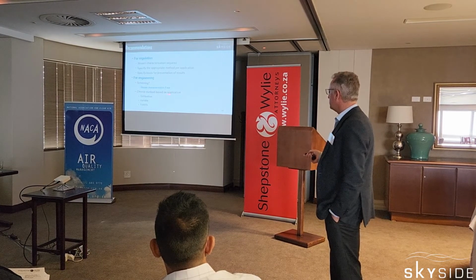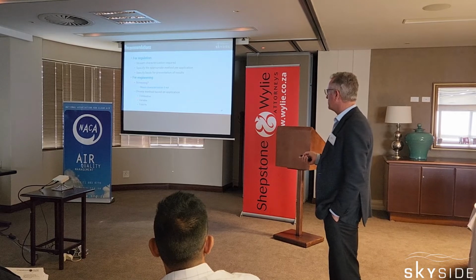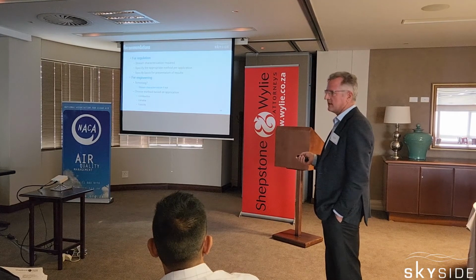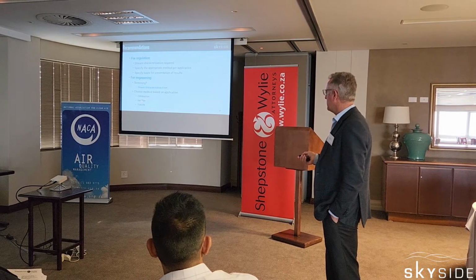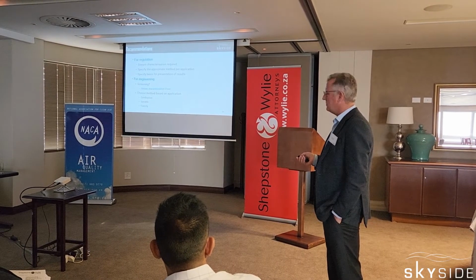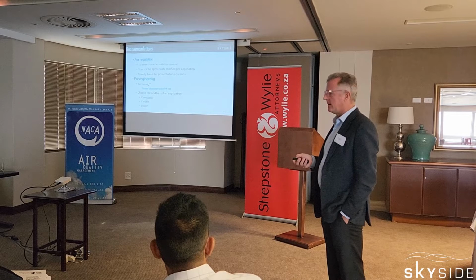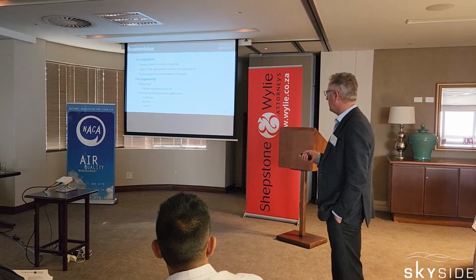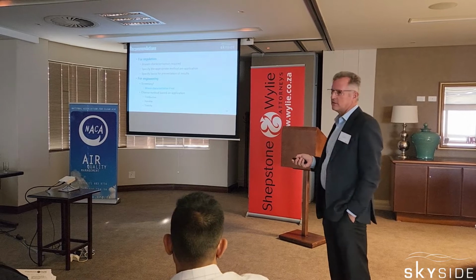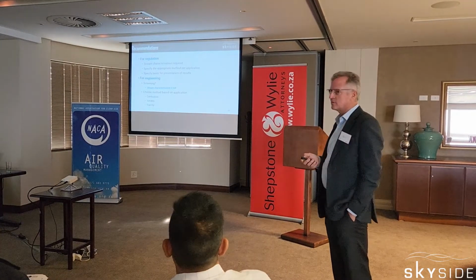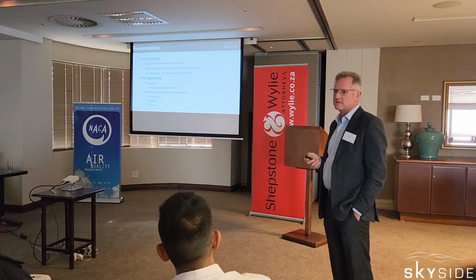And I think choose the method based on the application. For instance, whether there's combustion, again, FID would be a very useful way of measuring it. If it's variable, then you definitely need some sort of online technique like FID or NDIR. And if it's the toxicity that's in question, then you definitely need to use something like method 18 to make sure that you understand all the issues.